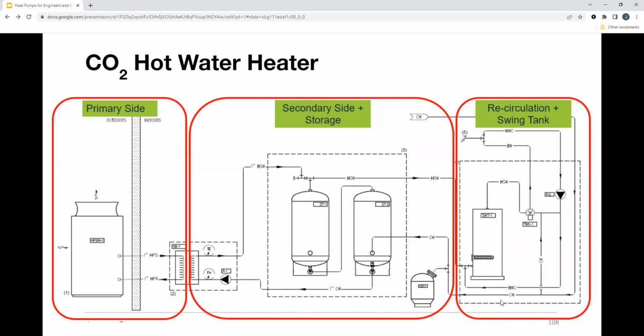And this is what the overall system looks like. It is a centralized system. There are smaller split systems out there for an electric scale, but if you are trying to do a domestic hot water centralized system for your whole building, this would be an option for you, right? You have your primary side here. This is your heat pump on the outside. Then you have your hot water piping going to this heat exchanger. It's a really small heat exchanger, but it is necessary. If you are looking for it on the mass plumbing board, this is not what's rated on there. It's actually this heat exchanger that's there because it's touching the potable water.